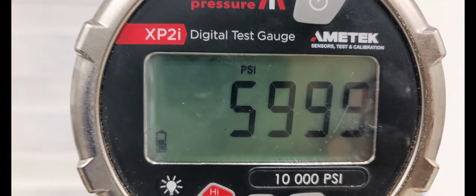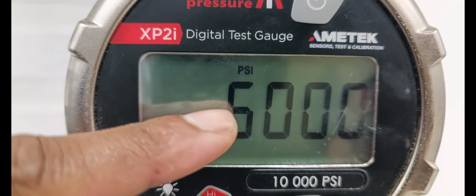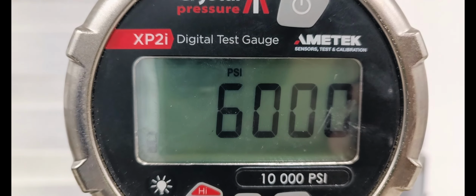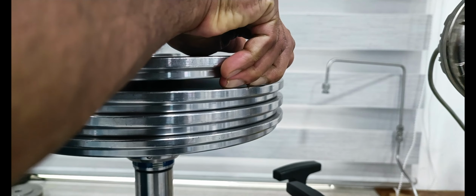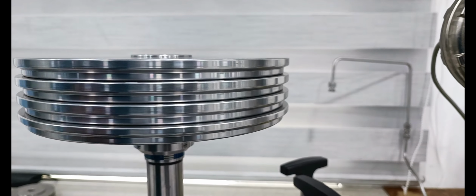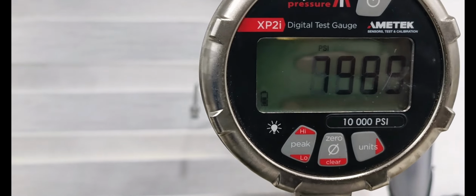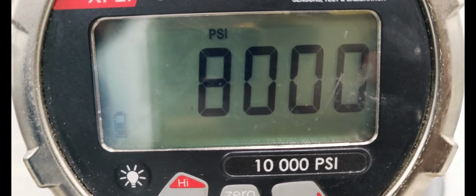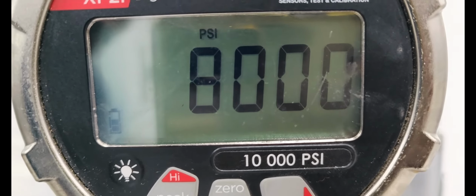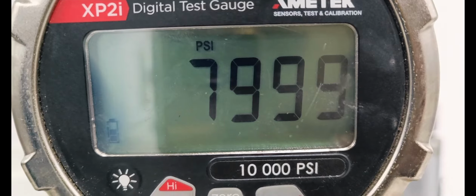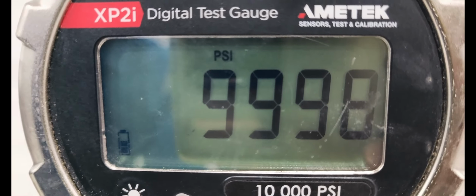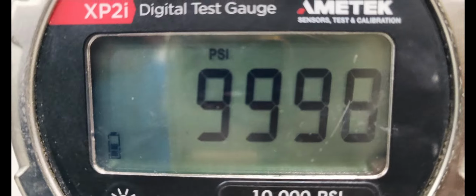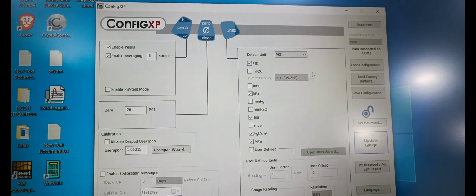Now the reference gauge is showing 6000 psi, steady. We are applying 8000 psi. Now the reference gauge is showing 8001 psi. Now the display is showing 8000 psi. Now calibration and verification is completed.